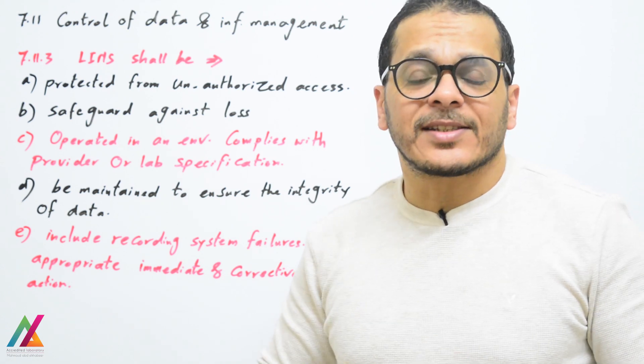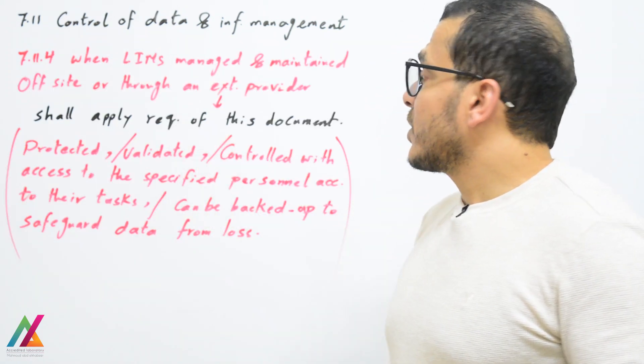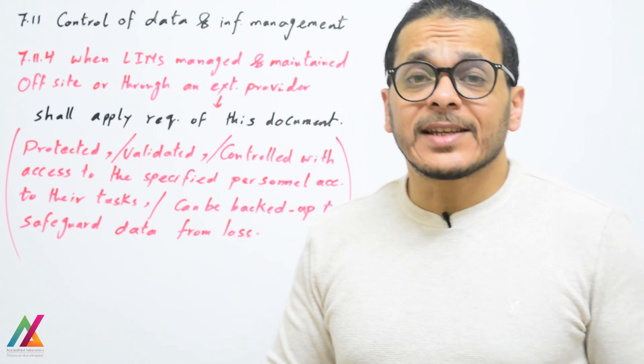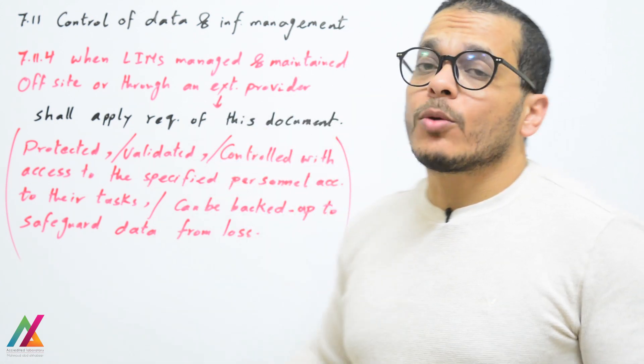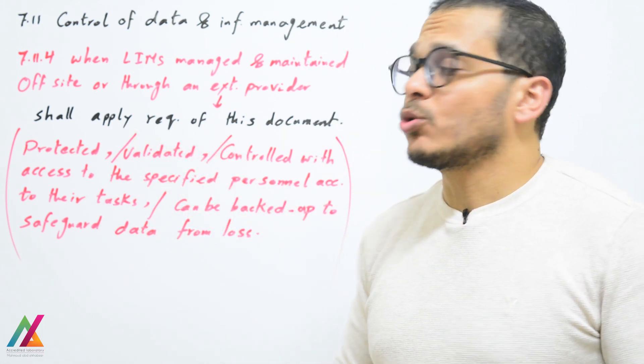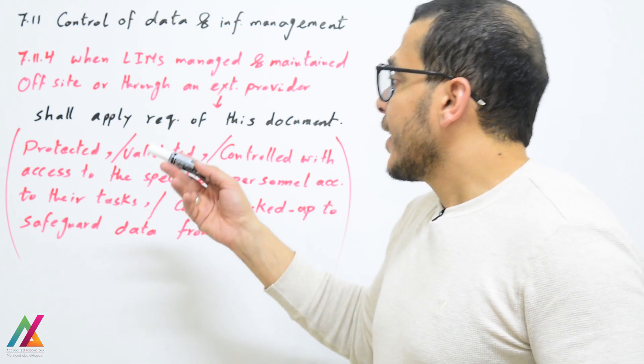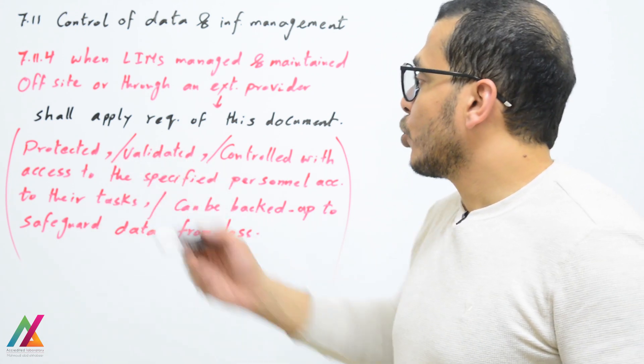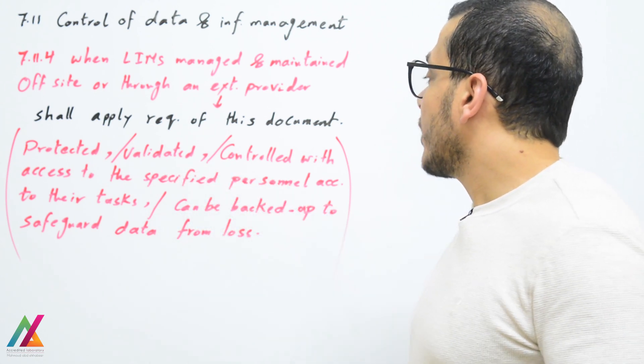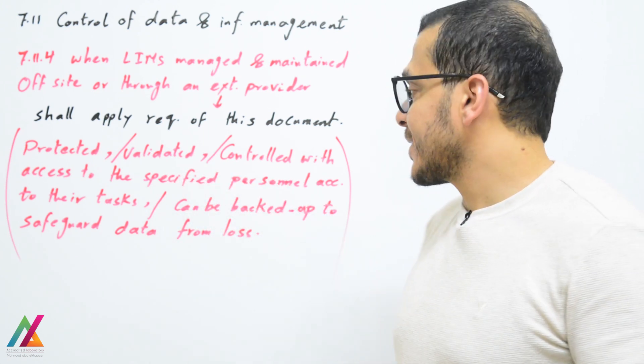When LIMS is managed and maintained off-site or through an external provider, this external provider shall comply with the requirements of this document and apply all requirements such as: the software shall be protected, validated, controlled with access to specified personnel according to their tasks, and backed up to safeguard data from loss.